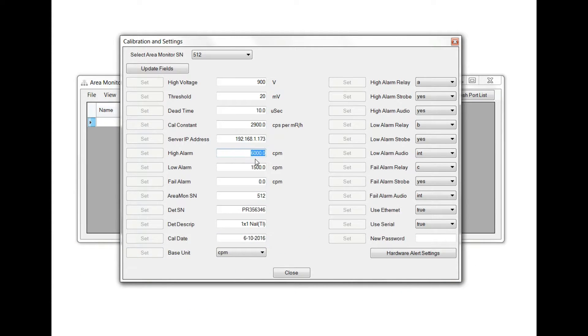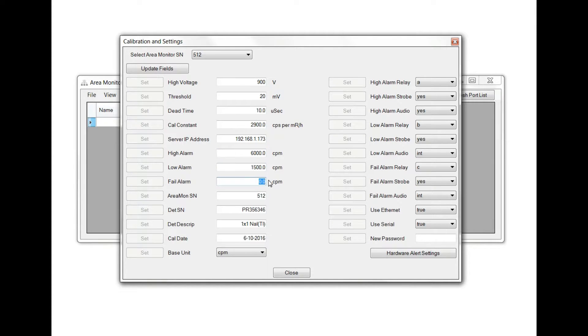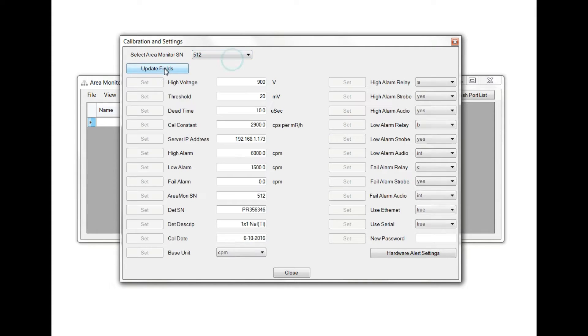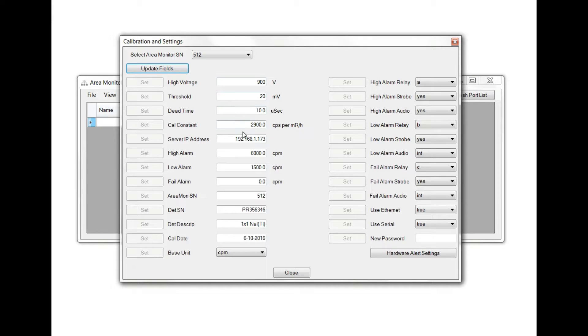From the Calibration and Settings screen, you can change your high alarm, low alarm, and fail alarm. You can select your area monitor and click Update Fields. This will populate the fields with the settings of the area monitor you selected from the drop-down menu.